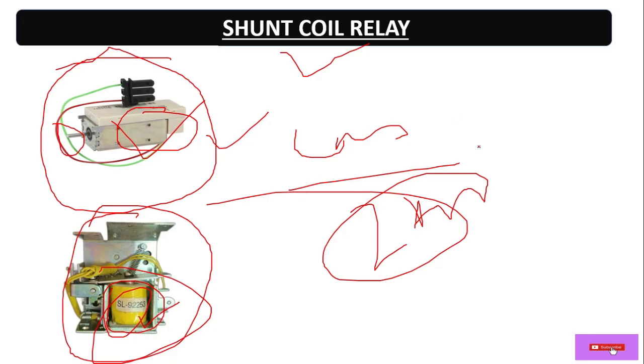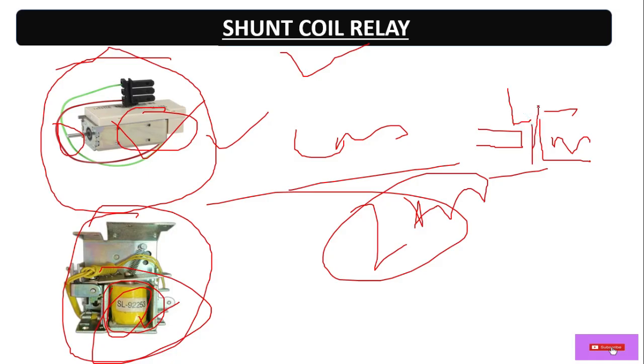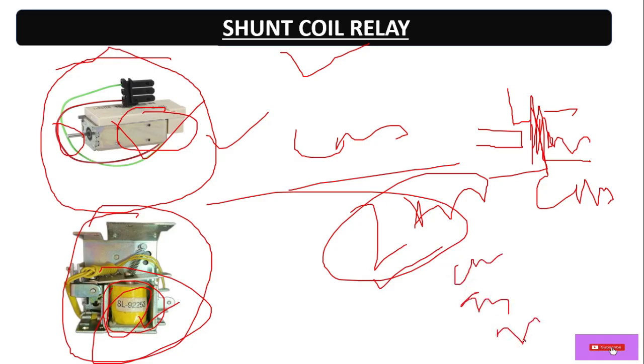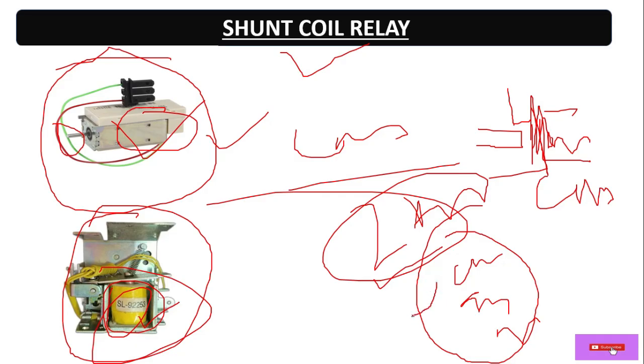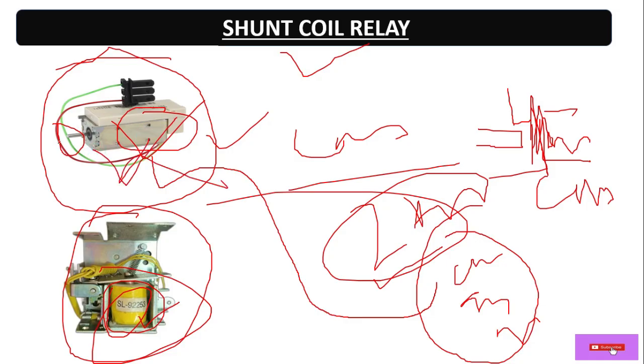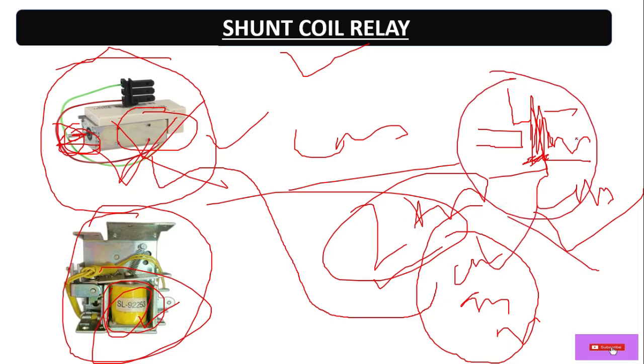The shunt coil is basically used to trip the circuit. In the ACB there are two contacts — one is moving and another is fixed. If the circuit is in a closed condition and we have any fault like overload, short circuit, or earth leakage, the micro logic controller will activate this shunt coil relay. It will hit the plunger, release the spring charge, and break the circuit. Simply put, the shunt coil relay trips or opens the circuit in case of any fault.